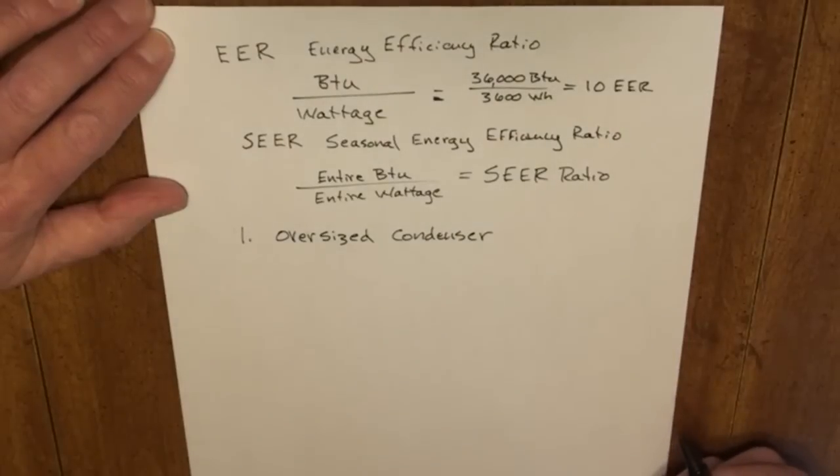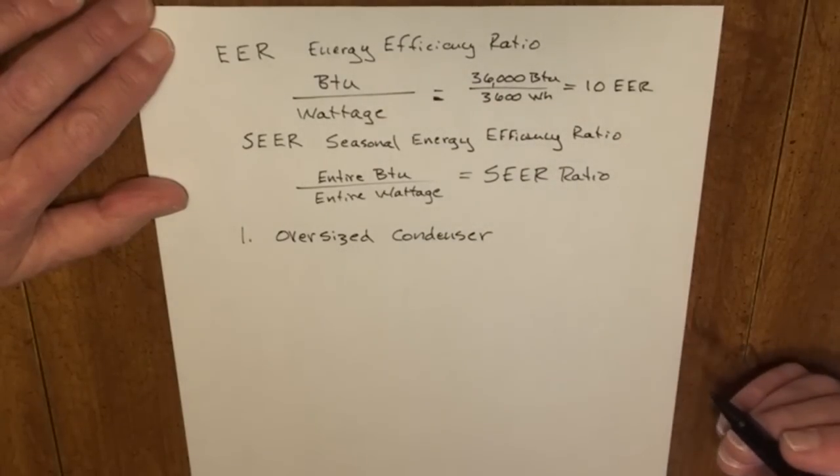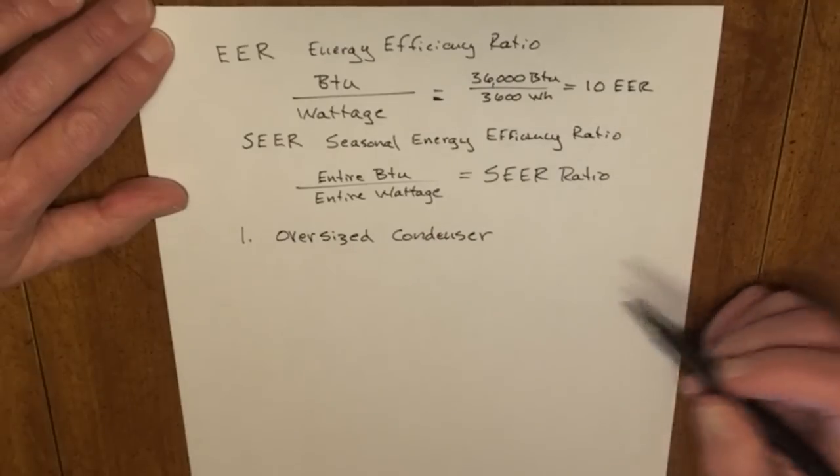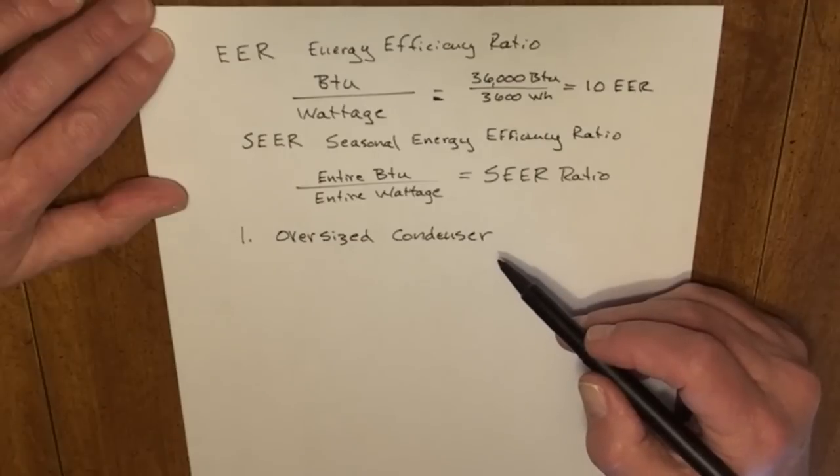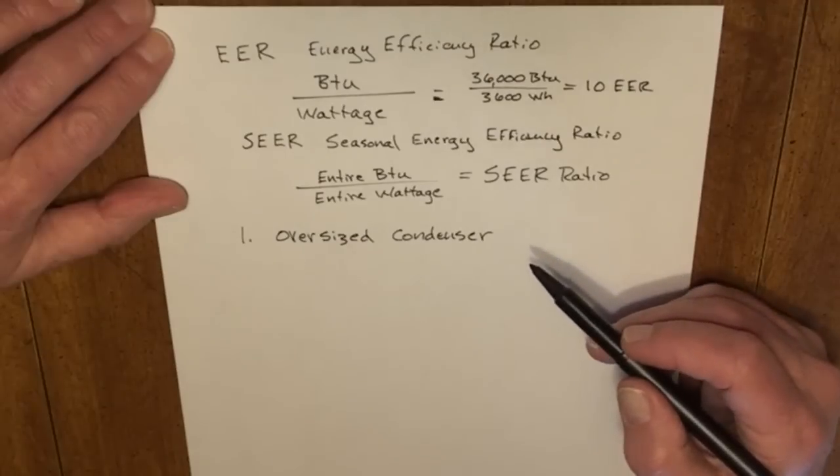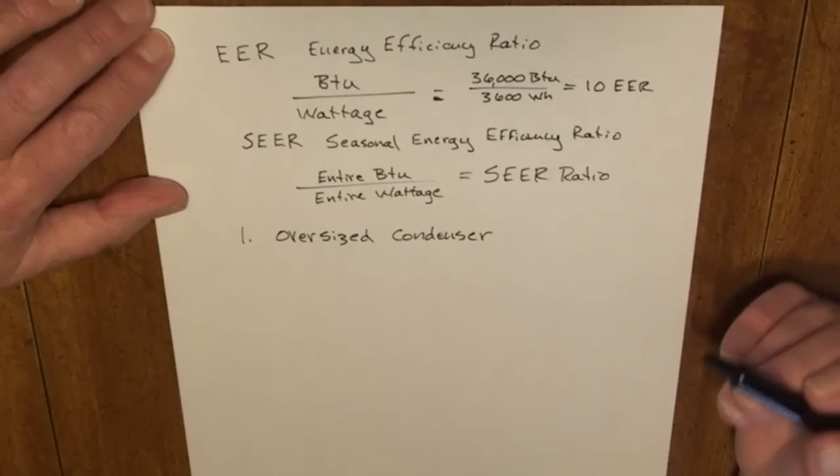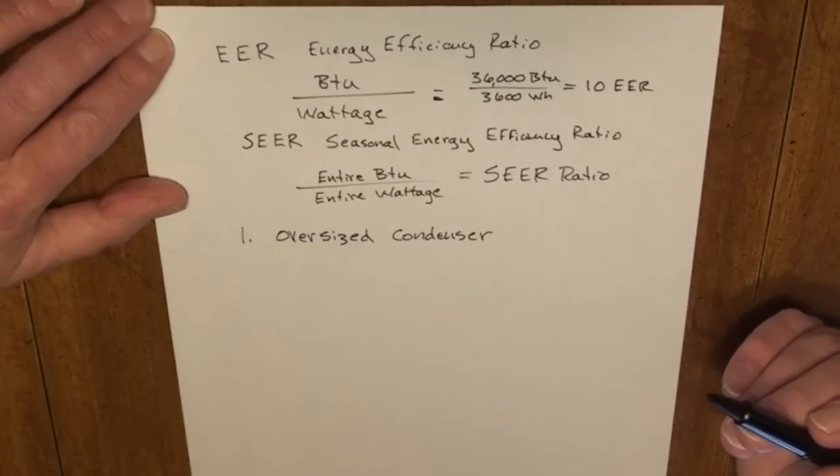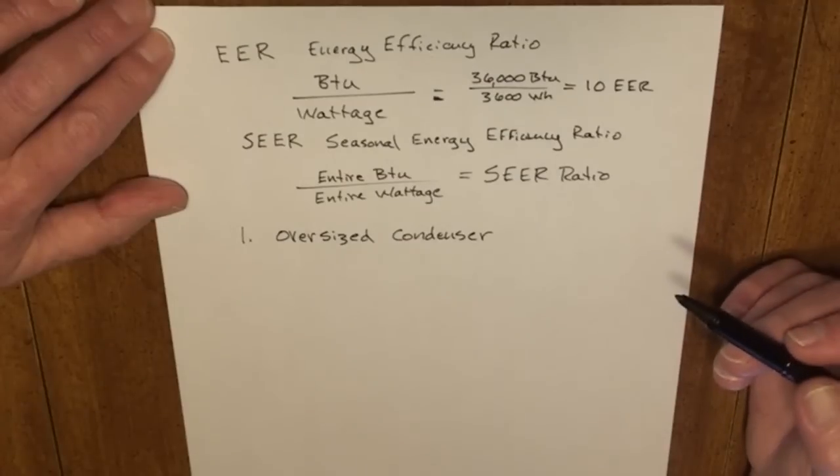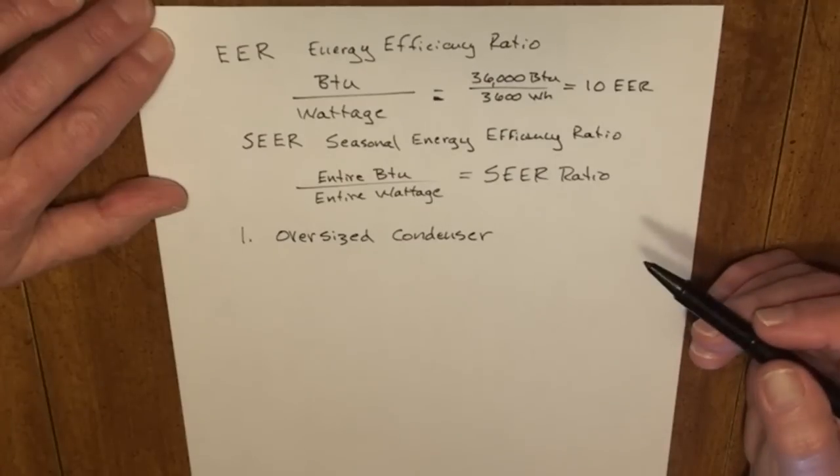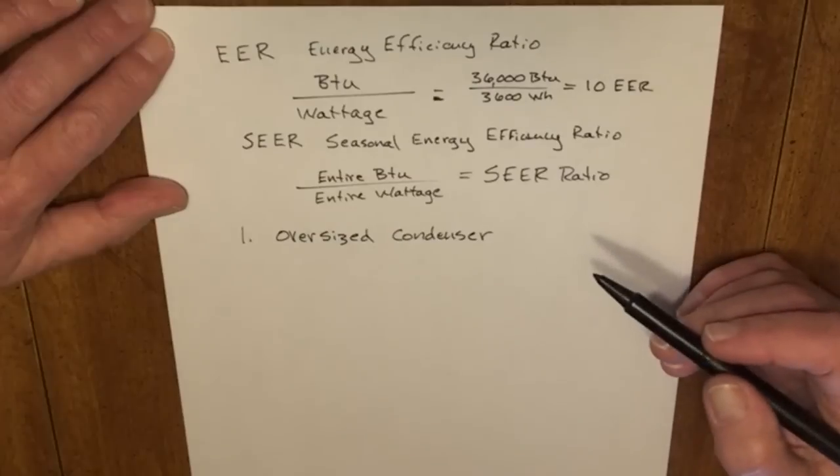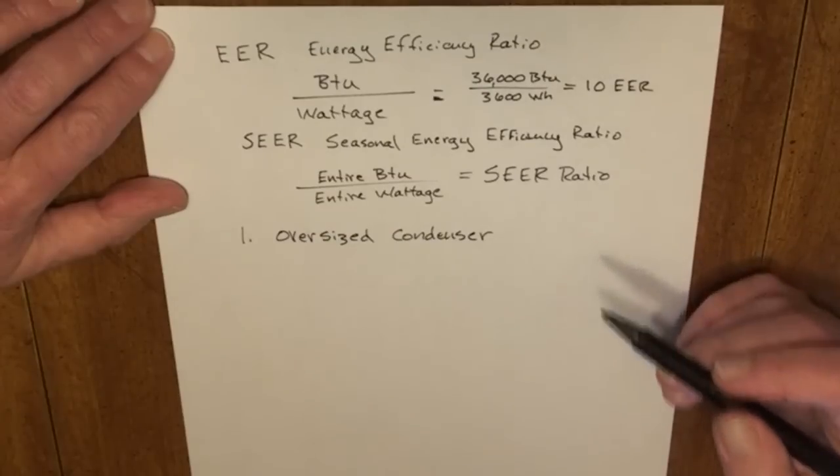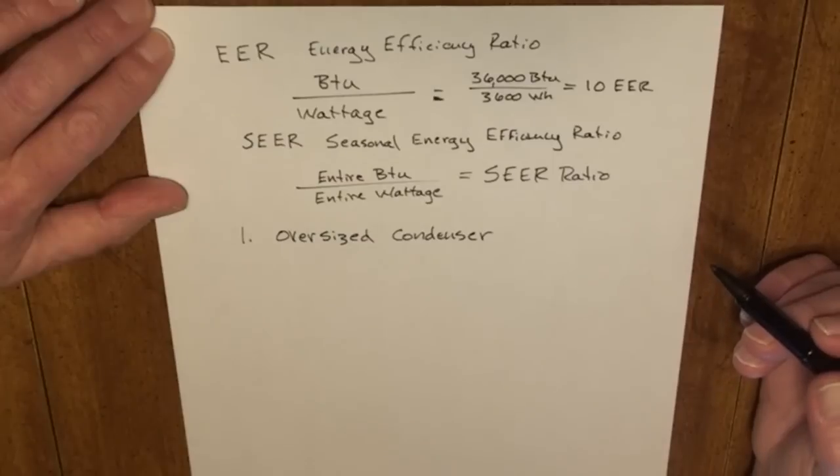The oversized condenser can be large enough to use a fixed orifice metering device and achieve the 13 SEER minimum rating. The oversized condenser allows the refrigerant to boil at a lower pressure. Lower pressure equals less work on your compressor, less work equals lower amp draw, and lower amp draw equals less wattage consumption.